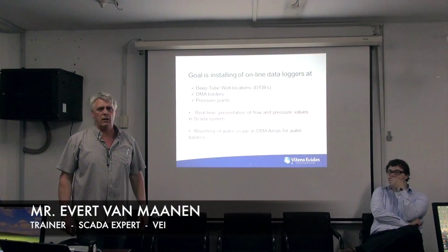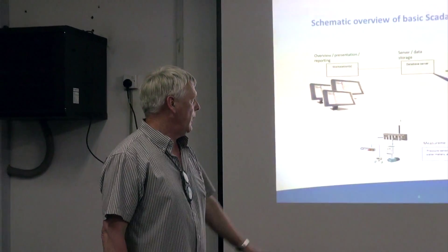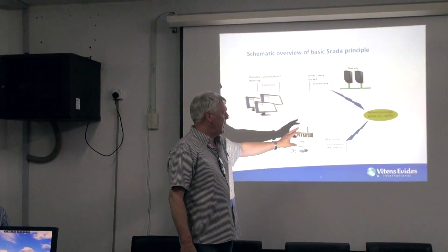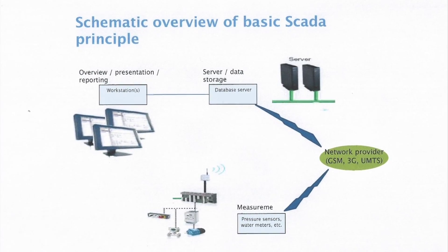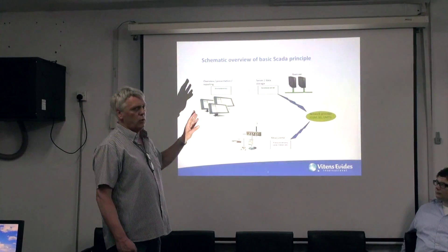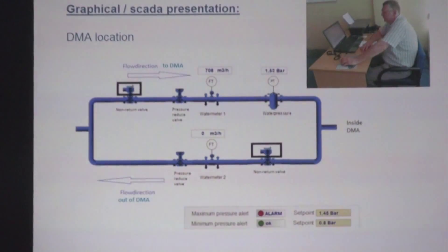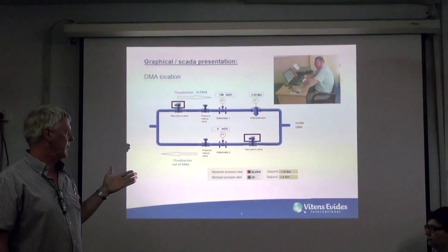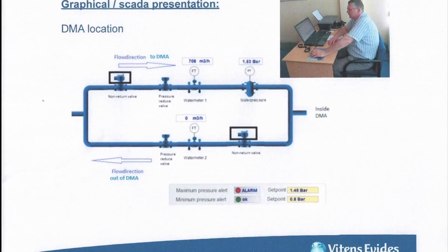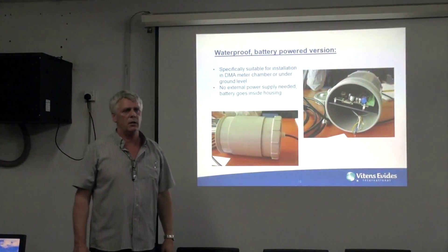The goal of this pilot is to install data loggers in Deep Tube Wells, DMA zones, and pressure points. This is a schematic overview of the system. In the field, the data loggers will send data via the mobile network to a data server. The data server can be located anywhere — it's not important where it's installed. You can then log in via the internet to the data server and get the presentations on your PC. This is a picture of a DMA zone showing how it could look in the future. The system can also present alarms that you can configure in the SCADA system.